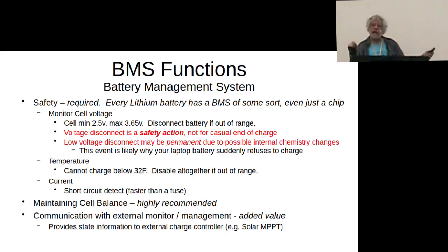Now, nickel cadmium, who cares? Lead acid, who cares? Lithium, you care. Because all of a sudden, that cell has gone below its minimum. There's a little chip inside that battery - it's not a full-scale BMS thing, just a little tiny chip watching the voltage. When that voltage gets below that critical level, it disconnects the battery permanently. You can't go back in there and jump start it. It's dead.